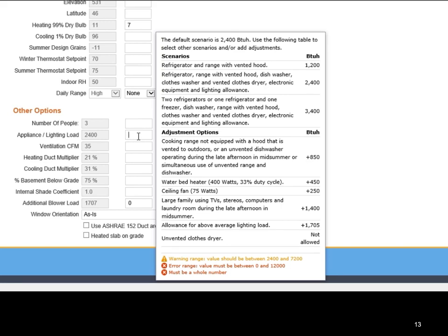That's a really good question. If you have a lot of internal gain, say if you have somebody with an aquarium, or somebody with a commercial kitchen in the house, you should consider it at that point. One thing I will point out is that appliances have gotten newer. The amount of waste heat that they contribute to the house has gotten smaller. And this has a pretty big impact on cooling, as I recall. Yeah, in this case it adds 2,400 BTUs to it.